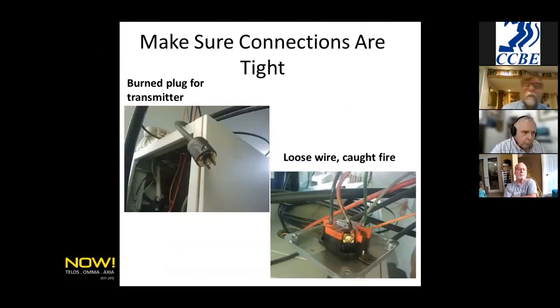Here's an example where they used a plug that was plugged into an outlet for the transmitter. It was a small transmitter mounted in the rack, and a loose wire caught fire and burned the socket and burned the plug.